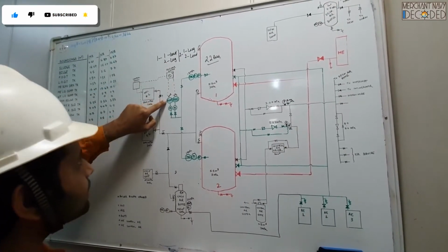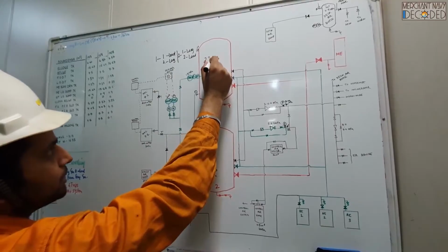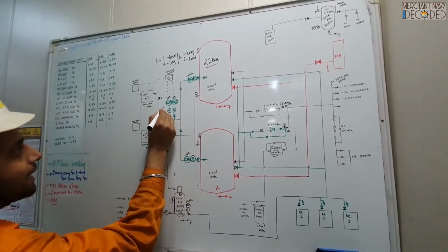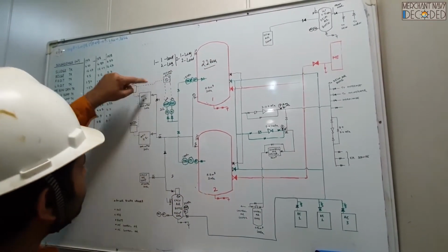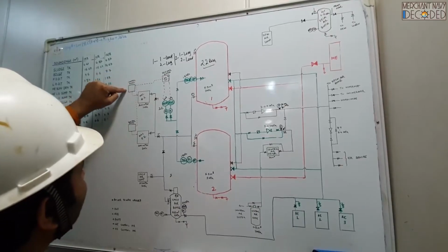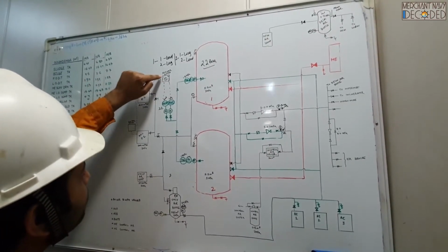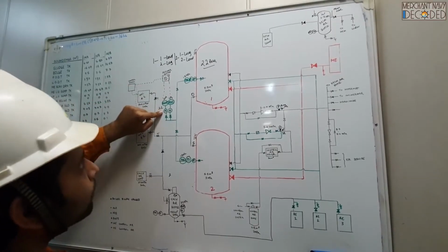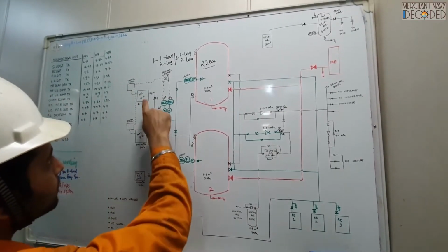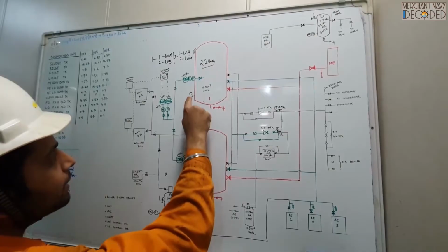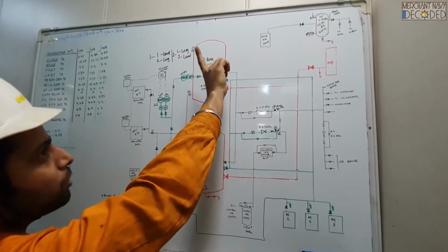So now the lead one says the pressure is right at 22 bar and it is set at 22. So it will give a signal to the control panel of number one over here. Why start the number one compressor? Because it is on lead and I have already reached 22 bar. So automatically this compressor starts and sends the air to this air bottle over here and the air bottle pressure starts rising.